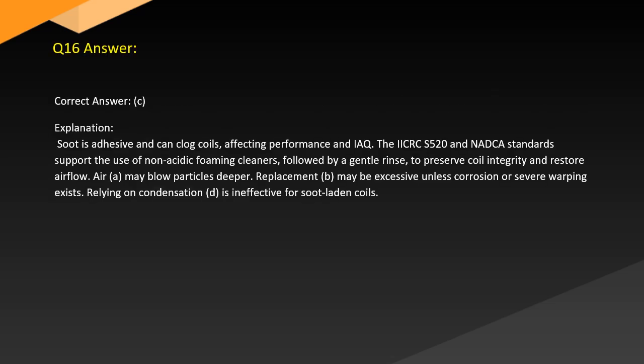Answer. Correct answer: C. Explanation: Soot is adhesive and can clog coils, affecting performance and IAQ. The IICRC and NADCA standards support the use of non-acidic foaming cleaners, followed by a gentle rinse to preserve coil integrity and restore airflow. A may blow particles deeper. Replacement, B, may be excessive unless corrosion or severe warping exists. Relying on condensation, D, is ineffective for soot-laden coils.